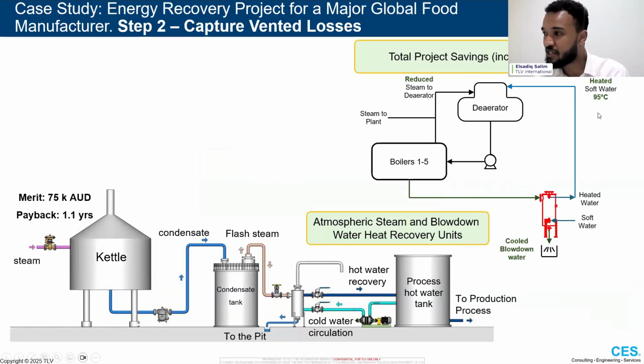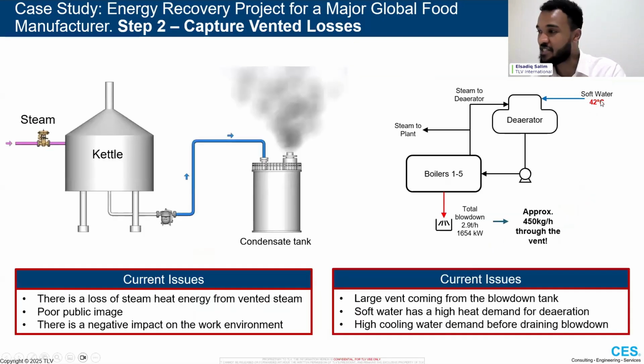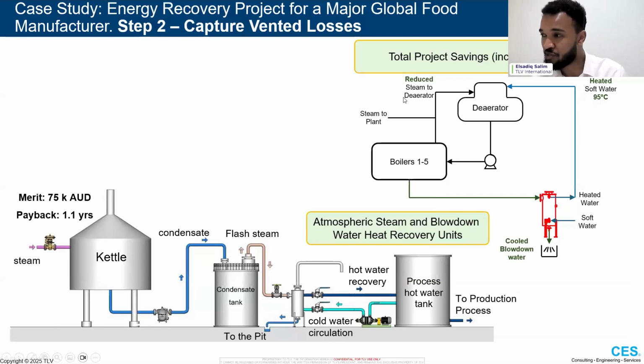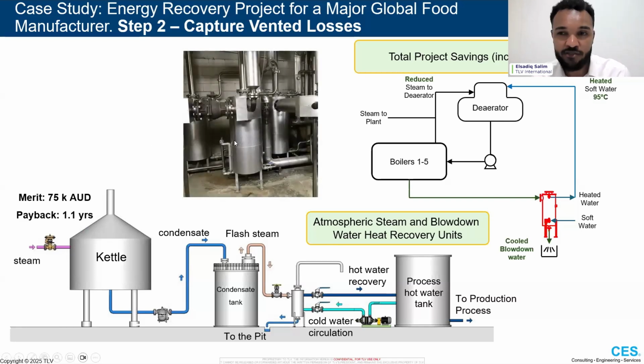And in this case, they managed to preheat their soft water going into the deaerator with that waste heat all the way up to 95 degrees compared to before where it was 42 degrees. So a massive saving for the site in terms of reducing the amount of steam they needed to preheat their soft water. Overall, this step and the condensate return case study we saw before was about 400,000 Australian dollars savings on that site. And then the other case is a very similar heat recovery unit, an atmospheric one you can also use on flash steam. This site used it to recover just the energy from their flash steam onto a nearby hot water user with a payback period of about 1.1 years, just over 1 year. And then this is an image of the heat recovery units.